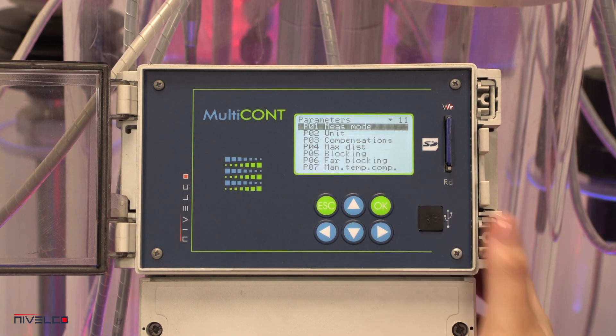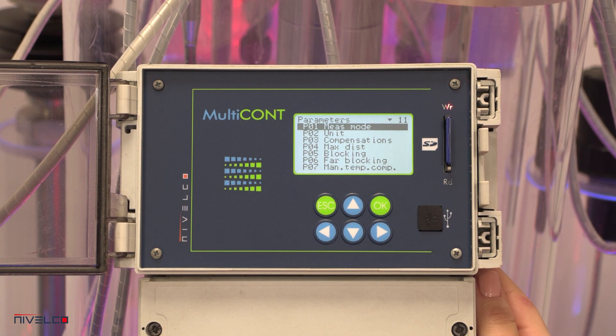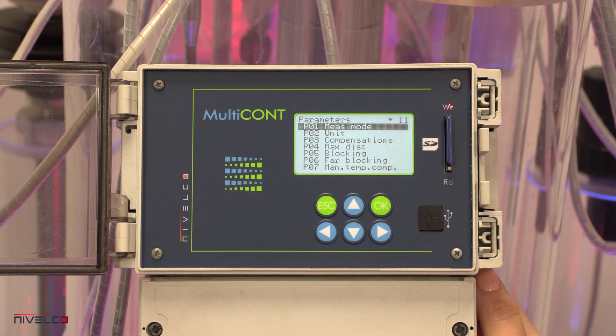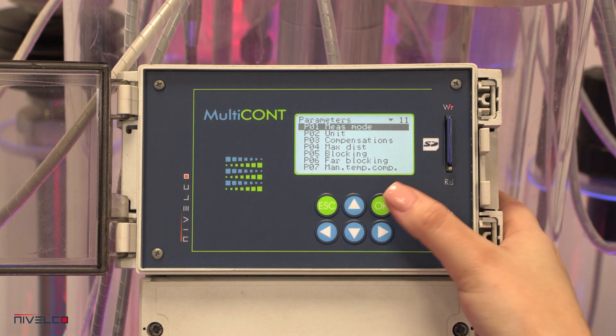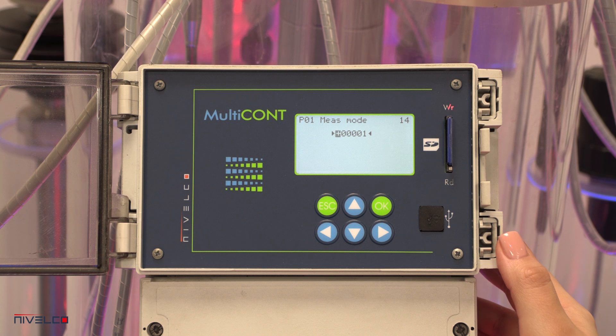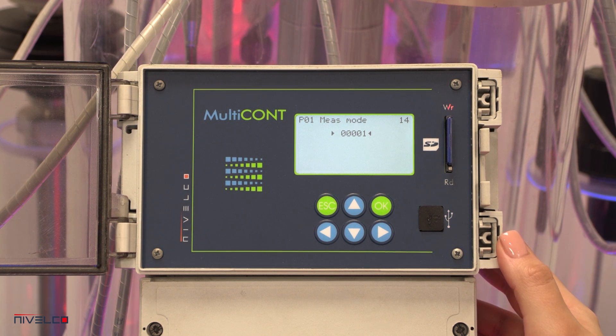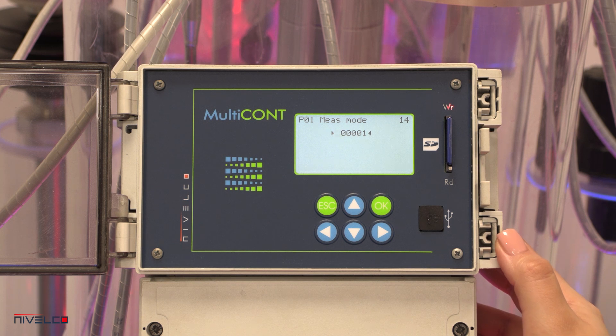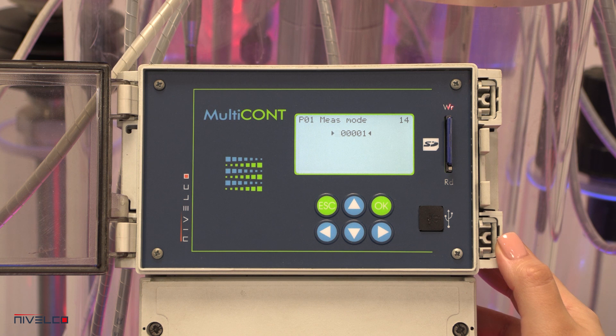The parameters are device specific — read the device programming manual for details, but we'll go over a few entries here. The P01 parameter's A value determines the type of measurement, which subsequently determines the values and their units. The default setting is 1, which means level measurement.